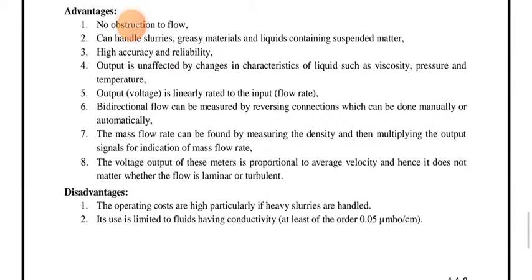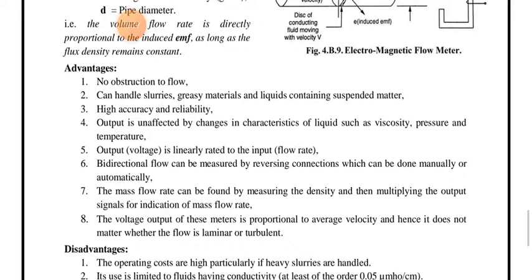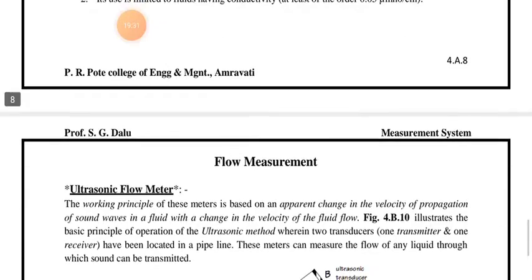Limitations of the electromagnetic flow meter: operating costs are high, particularly if heavy slurries are handled. It is also limited to fluids having electrical conductivity of at least 0.05 micromho per centimeter.